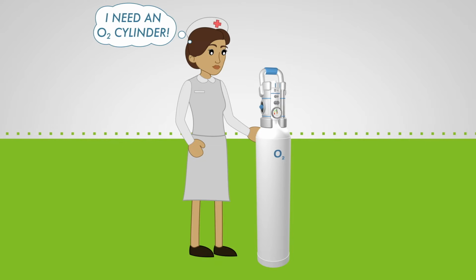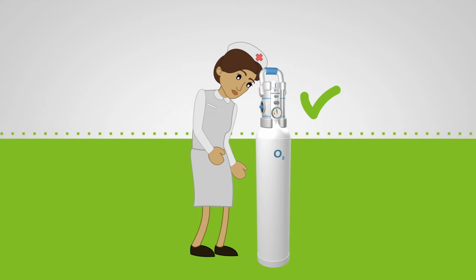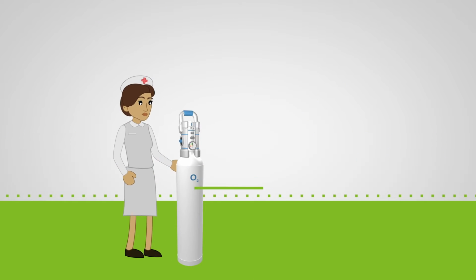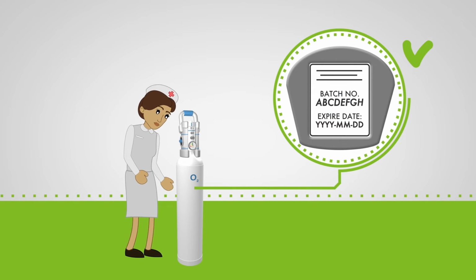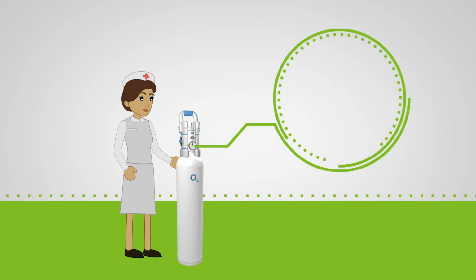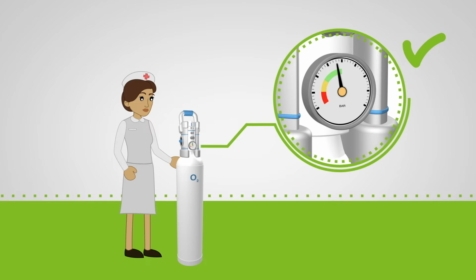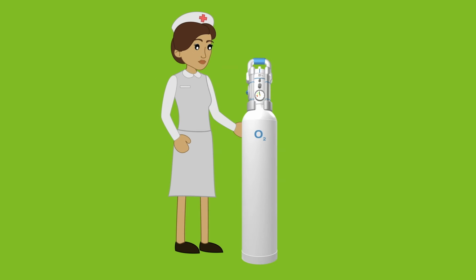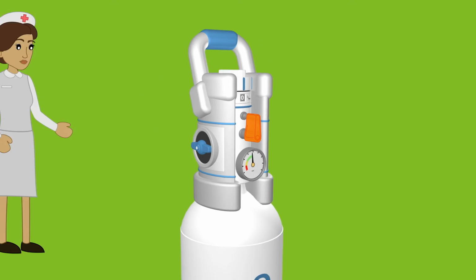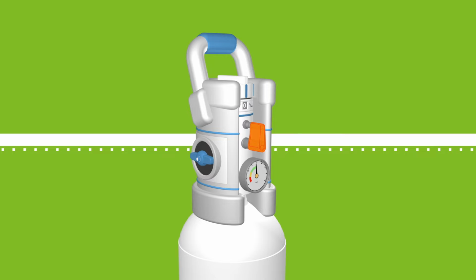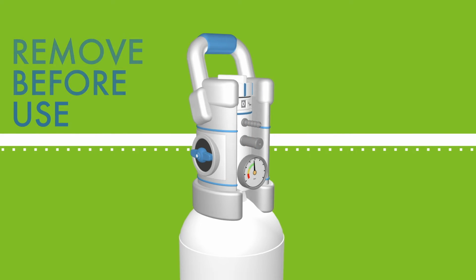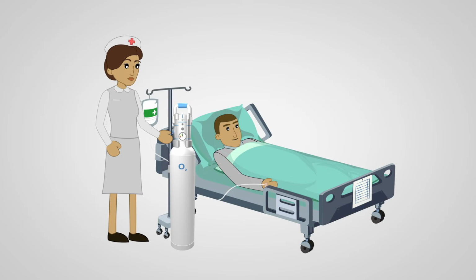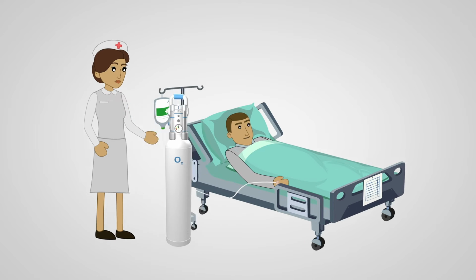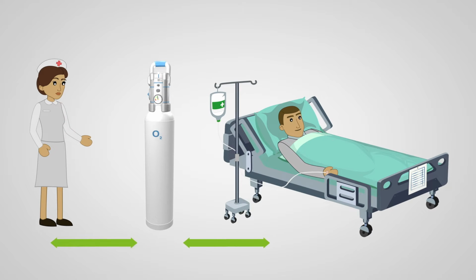Before using the cylinder, check that it is the right gas by checking the label, that the gas is within its expiry date, and how much gas is in the cylinder by looking at the contents gauge. If you are using a new cylinder, you will find it has a tamper-evident seal on the valve that you need to remove before use. Remember that the cylinder should be set up before use away from the patient, with the outlets facing away from both yourself and the patient when initially opening the valve.